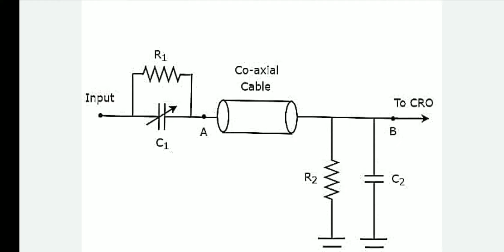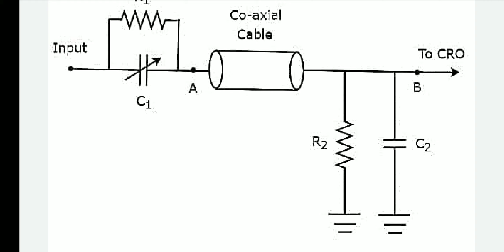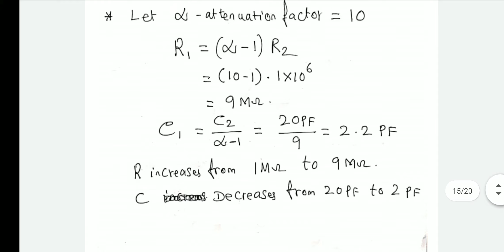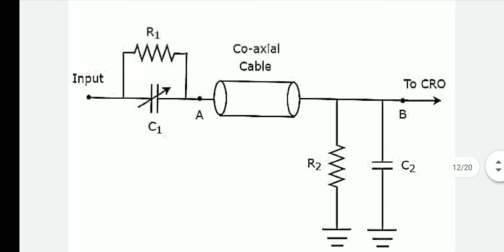And this capacitance, input capacitance, is 20 picofarad. I have to reduce the capacitance, so I am connecting here the capacitance value C1 as 2 picofarad. So when this 2 picofarad comes in series with the 20 picofarad, the effective capacitance is reduced. That is the idea. So that is how this passive probe is constructed. That is the 10:1 passive probe.